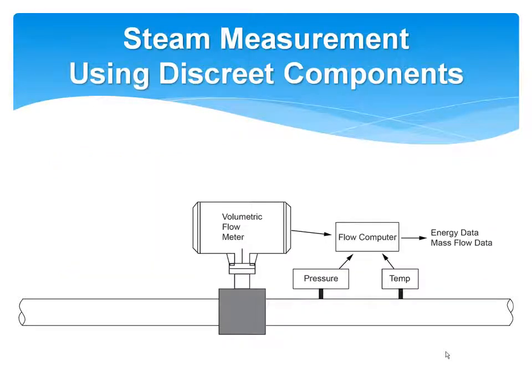So now that we've established the measurements required for getting to energy in steam, we look at basically you have a volumetric flow meter, a pressure sensor, temperature sensor. Those outputs are brought into a flow computer, and then you're calculating mass flow and getting energy data from the steam flow. Slide, please.